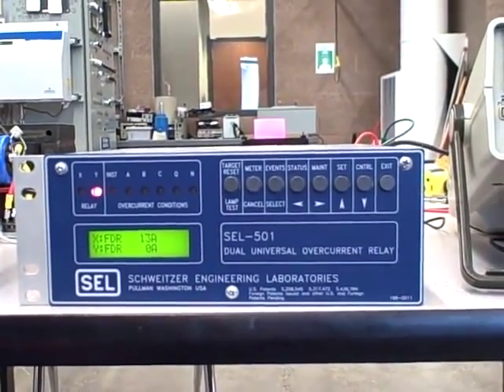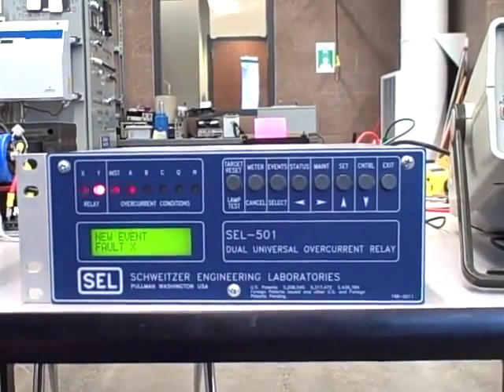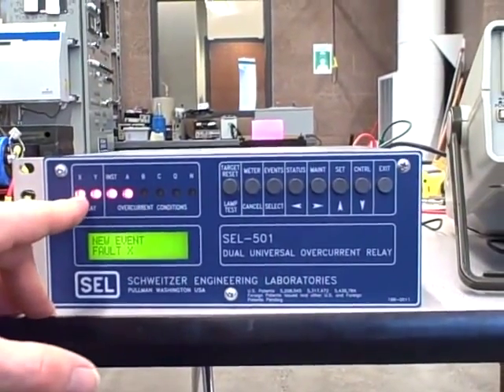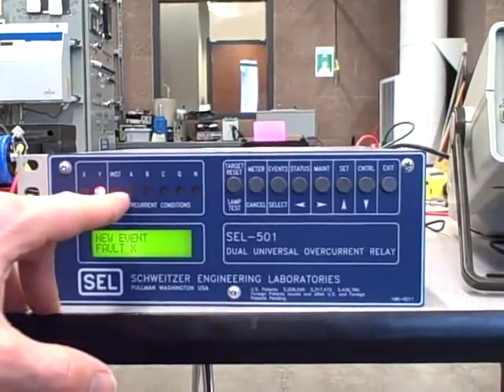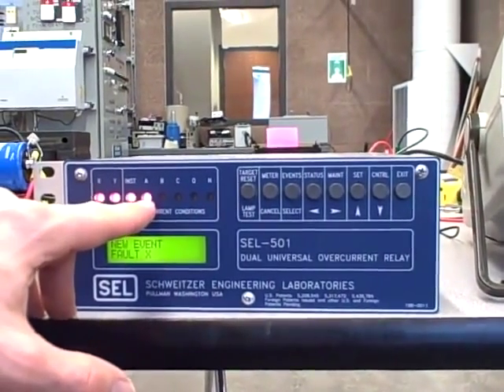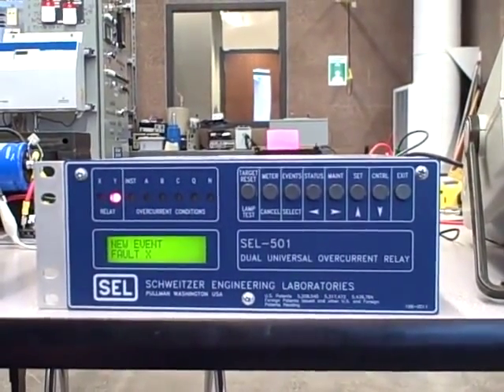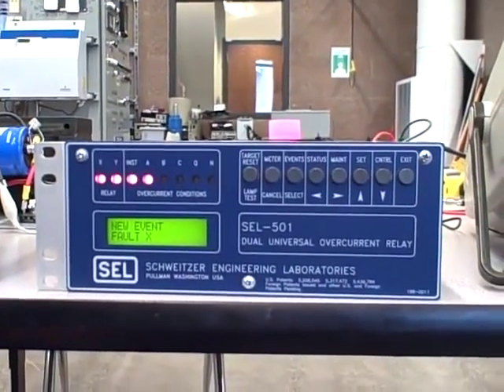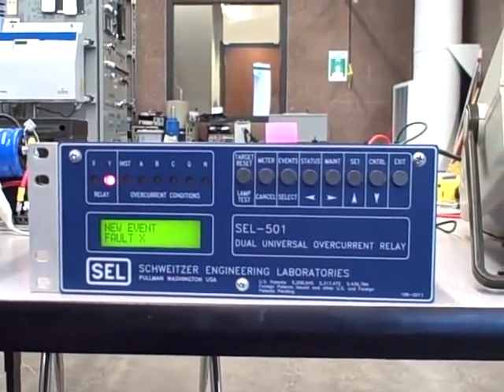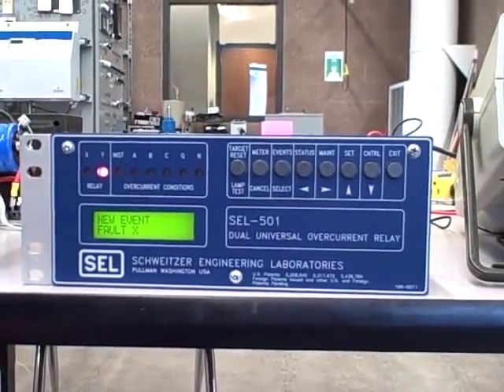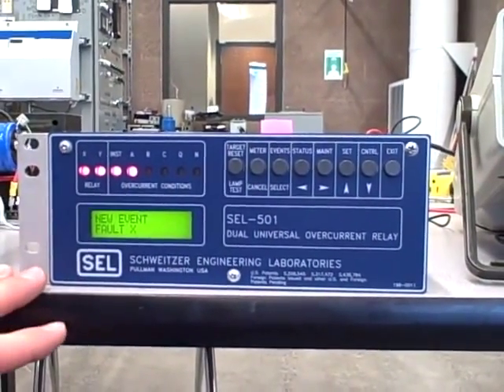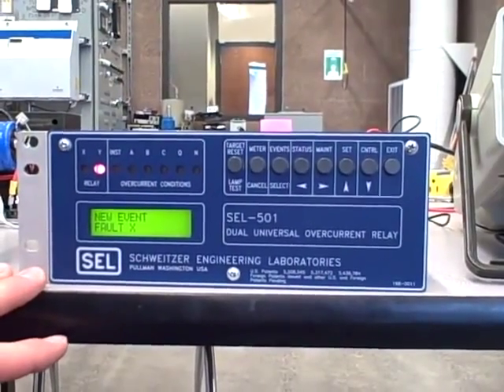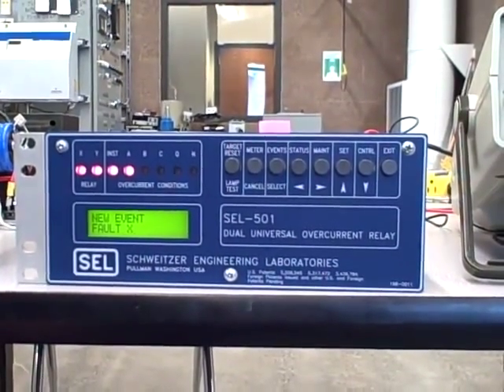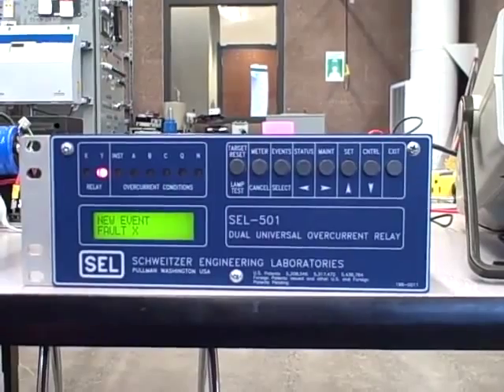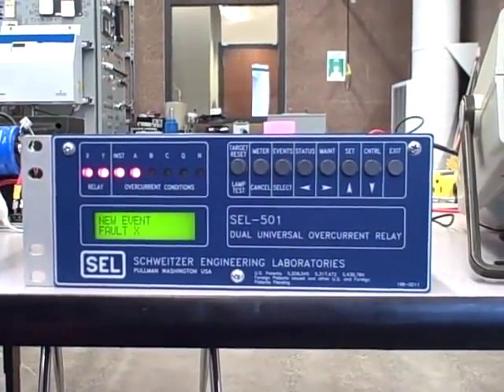When I turn the current back down, it stops beeping at me. So right here it says that relay X detected an instantaneous overcurrent condition on phase A and tripped out the breaker on that basis. And so that's a simple demonstration of a Schweitzer SEL 501 overcurrent relay. Like I said, it's a very capable unit. There is a lot more functionality to this than we've touched on here, but just to give you a side-by-side comparison of how these two devices function, what their purpose is, it's an interesting illustration.